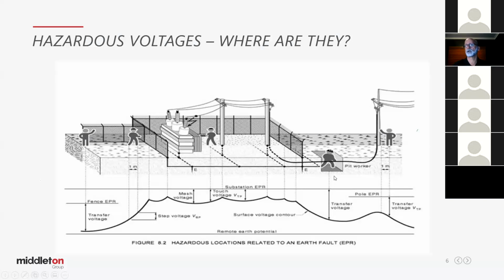We've got a maintenance worker over here that perhaps is servicing the earth or the sheath of the cable, an out of service cable, obviously. If there's a fault at the switch yard at the time, he may experience the difference in voltage. It's transferred through that cable sheath to him and his feet at the soil voltage. So quite a large transfer voltage there, you'll see.